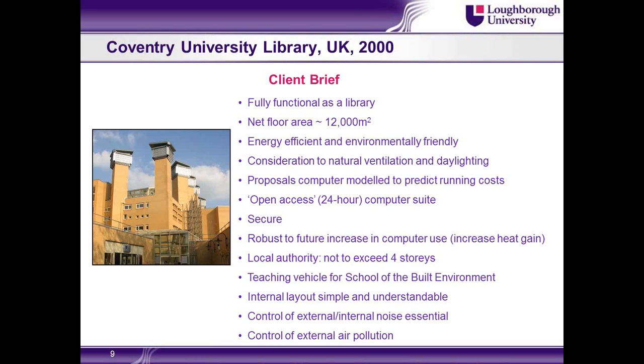Just picking up the highlights here, they wanted the design to be robust to future increases in computer use, so they were worried about increased heat gain. What happened there was we moved from CRT monitors to flat screen technology, so actually the heat gain reduced. So that was no longer a problem for us. What we were a bit worried about was the driving force got reduced. Because the heat output was reduced, so we were worried about whether we could drive enough ventilation flow. So some real interesting points of development there.